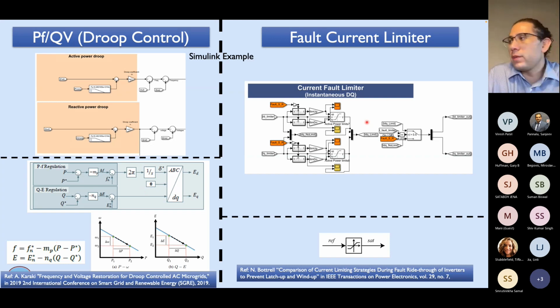On the left-hand side, we show the implementation in Simulink, but on the bottom, we can see basically what is happening. So we have an inverter, and they have low thermal inertia. So when we have current passing through them, sometimes it can be very high, and this will damage the semiconductors and compromise the operation of the inverter.